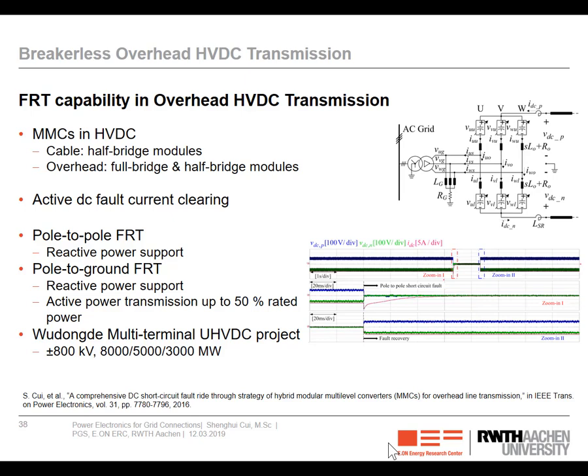So previously there are only half-bridge modules inside, but here we will mix both the full bridge and the half-bridge. I will not go into much detail, but the nice thing is, as long as we mix the full bridge and the half bridges in this converter, then it is possible to manipulate this DC link voltage to any voltage we want. Because for a normal voltage source converter, we know that when the DC link voltage is zero, then it's impossible to control the AC side current, right?